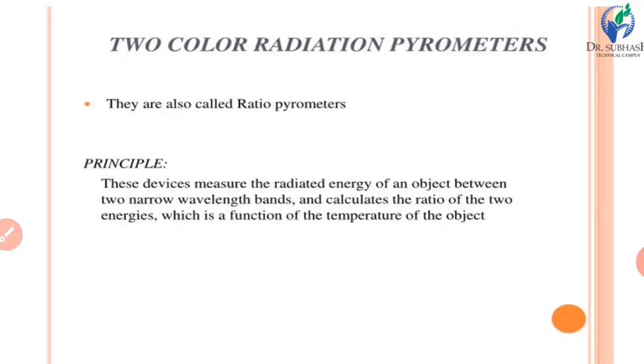Now another pyrometer is the two color radiation pyrometer. They are also called ratio pyrometers. What is the principle behind this? These devices measure the radiated energy of an object between two narrow wavelength bands and calculate the ratio of the two energies, which is a function of the temperature of the object. So this is the principle for two color radiation pyrometers.